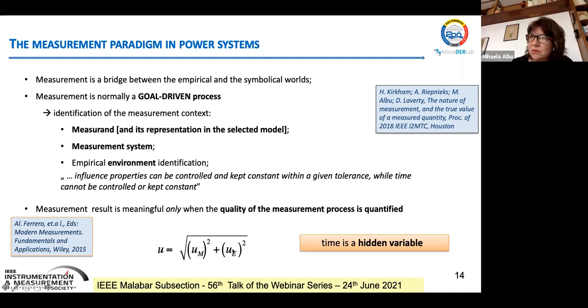One of these two components is the uncertainty associated with the measurement equipment, and this is usually the only one that we compute. Let's say you used a smart meter class 0.2, which is the norm in smart grids today. This means we can compute the uncertainty as 0.2 divided by the square root of 3, for instance.